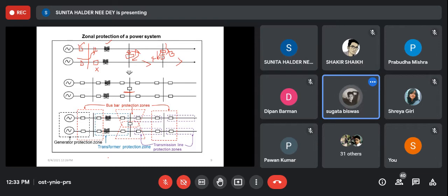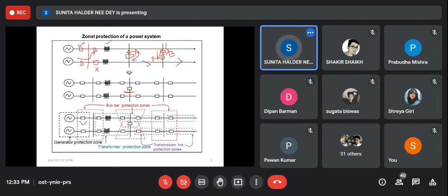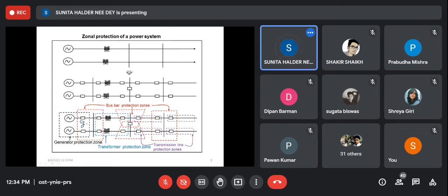Now you see here, say this generator, this relay. Let me write G1. Say this is G1, giving the primary protection to generator 1. What is the meaning of primary protection? If there is a fault in the generator, it is expected that G1 should operate first. But say, due to a problem in the relaying or in the circuit breaker, it has not operated. Then what will happen? Shall we allow it to continuously drain current into the short circuit? No. Then next, what should we expect? That this relay T1 should operate.